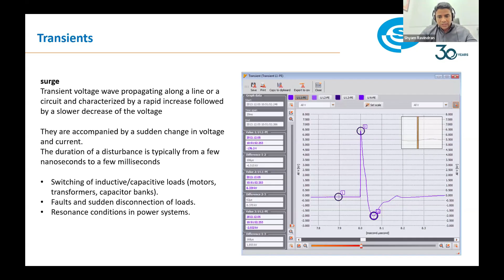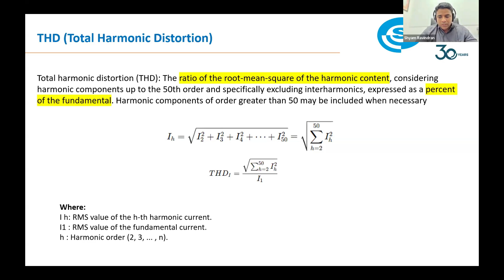Then there's the definition before and the definition now. Even now this is applicable, but from the regulatory perspective the definition for TDD is slightly modified. From the total harmonic distortion point of view, this was the regulation in place, applied by customers as well: the ratio of root mean square of harmonic content divided by the percentage of the fundamental. This was the methodology used to measure harmonics and design solutions.